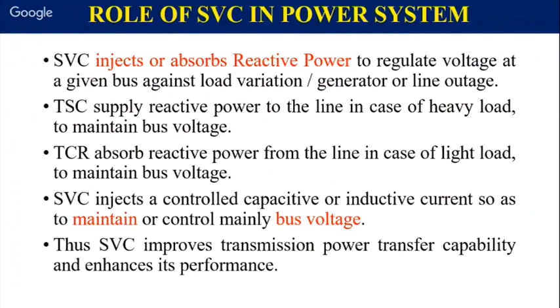So for that, thyristor switched capacitors are used. They are capacitor banks, but they are switched by thyristors in case of heavy load to maintain bus voltage, and there is the thyristor controlled reactor. See, capacitors are always switched. You cannot control a capacitor bank simply. You can either make it on or off. But if it is a reactor, you can control its impedance by varying the delay angle. Are you getting it? Capacitor banks can only be switched in and out. They cannot be controlled, whereas reactors can be controlled by changing the delay angle, the firing angle.